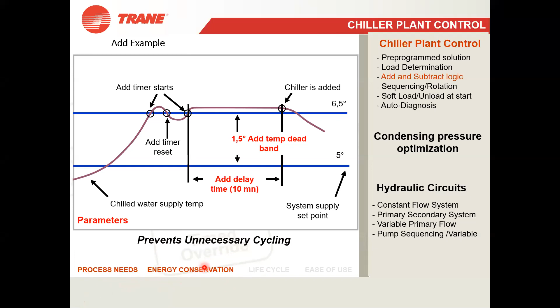So by doing this, what are you actually achieving? This prevents unnecessary cycling. That is one thing. And the major important thing is that you are saving your electricity cost. All the chillers are not running. When one chiller is switching on, accessories are also switching on, pumps are switching on, the condenser pump is switching on, and the cooling tower is getting loaded more. So you can see the process needs are being met, and energy savings are also being achieved at the same time.